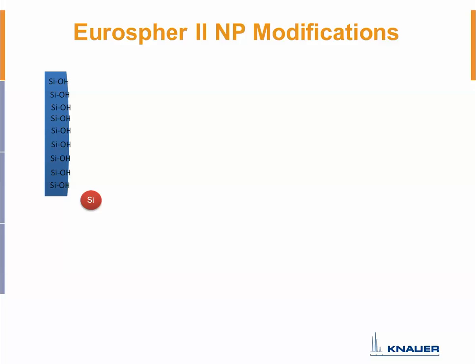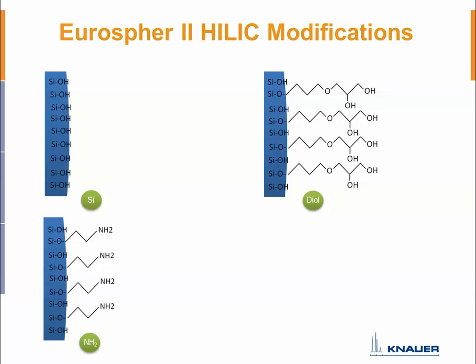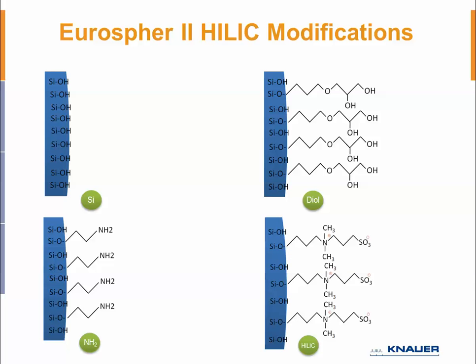Now let's have a short look at normal phase columns. In normal phase mode, you typically use bare silica gel phases, diol phases, amino phases, or cyano phases. In normal phase, you use hydrophobic eluents and your molecules interact with these polar phases — the reverse of reversed phase mode. HILIC columns use nearly the same stationary phases as normal phase, but with a completely different eluent, exploiting the hydrophilic interactions of analytes with the phase and with an aqueous layer on the phase. Knauer also offers a zwitterionic phase for HILIC mode.